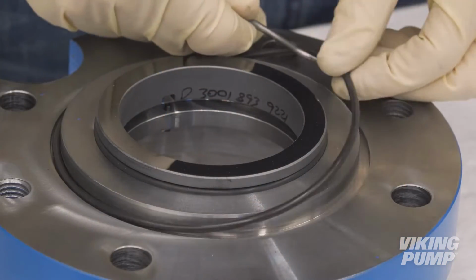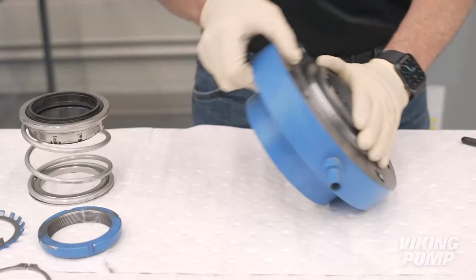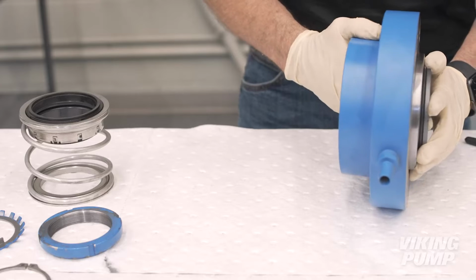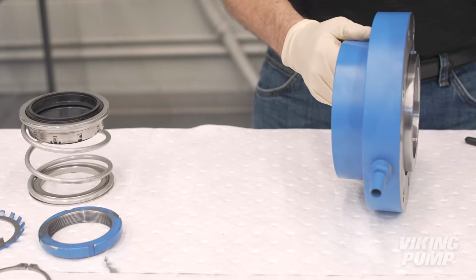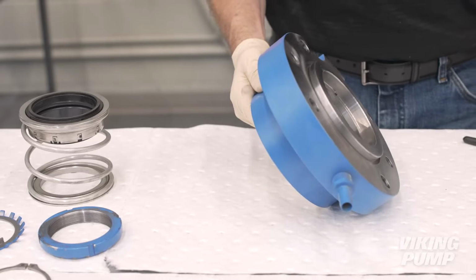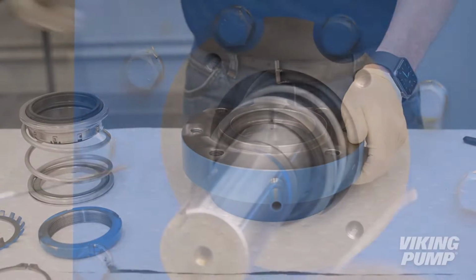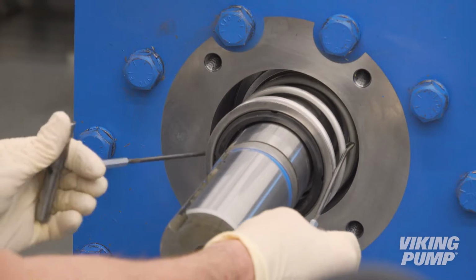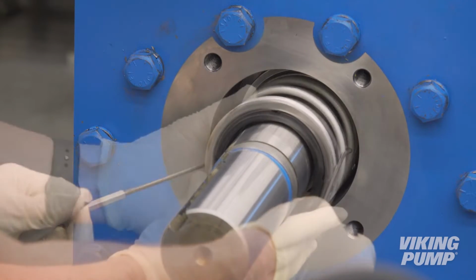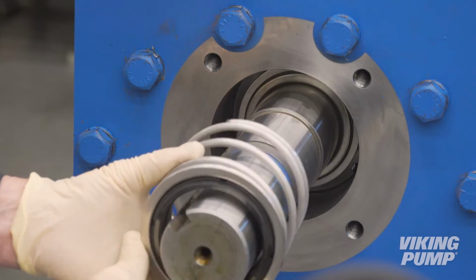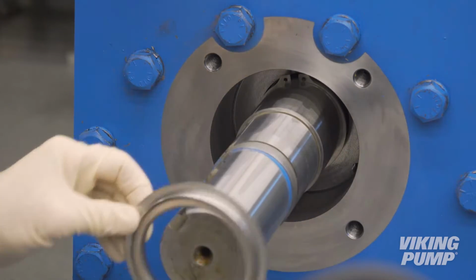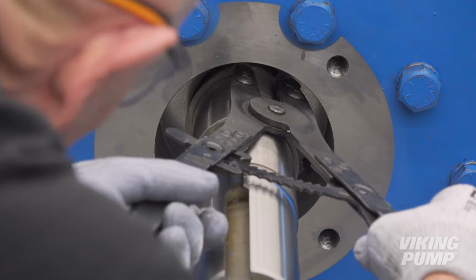Remove and discard the seal holder O-ring and the stationary seal seat. Retain the seal holder for reassembly. You can now remove the rotary seal components. Break the grip of the bellows seal by using a pair of picks. Remove and discard the seal components. Remove and discard the snap ring.